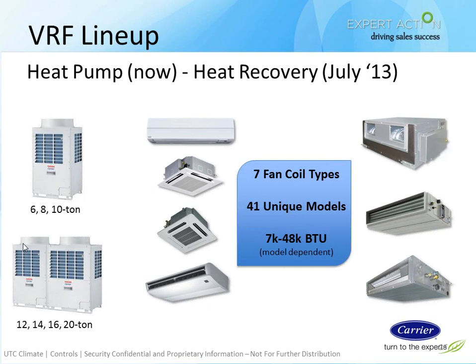we have outdoor units and we have indoor units, and those come in 6, 8, and 10-ton units, and those can be combined in 12, 14, 16, and 20-ton capacities. The indoor units, we see the variety there. We have the high walls, the ceiling cassettes, both in 2x2 size and about a 3x3 size, ceiling suspended, and the ductable units. That's 7 fan coil types, 41 unique models, and they come from 7,000 BTUs. That would be the high wall unit on the upper left, all the way up to 4 tons with that largest ducted unit on the right.